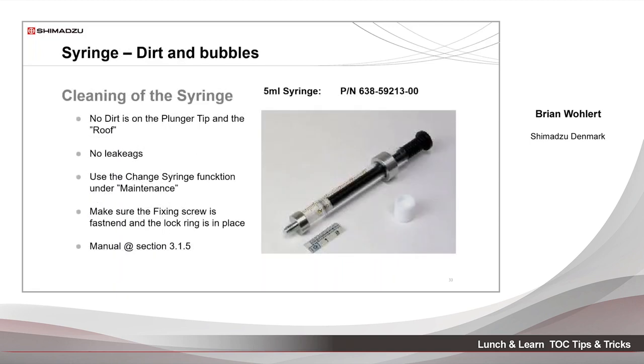A very crucial part in the system is the syringe. It's very important to maintain this if you would like to have reproducibility on the results. One of your daily routines should be to check the status of the syringes. Dirt can cause bubbles to stick to the surface of the Teflon tip. It will also cause bubbles to stick to the roof inside the syringe as well.